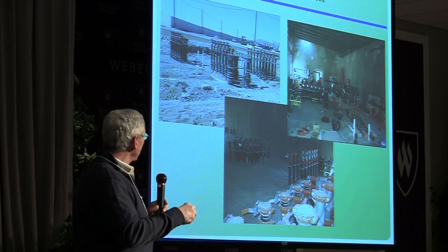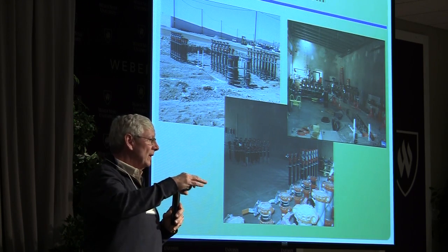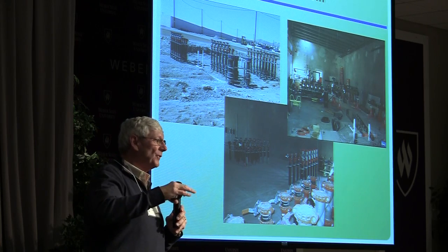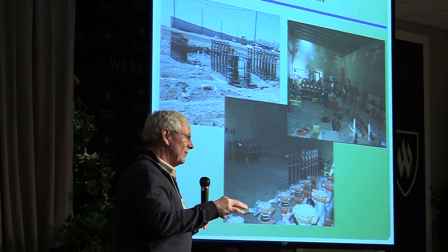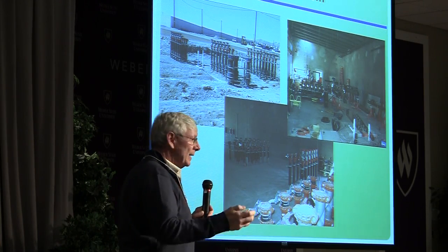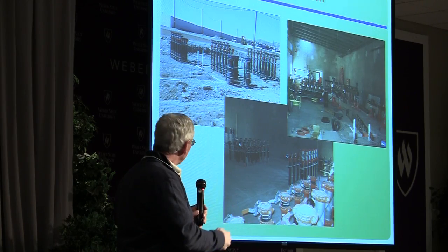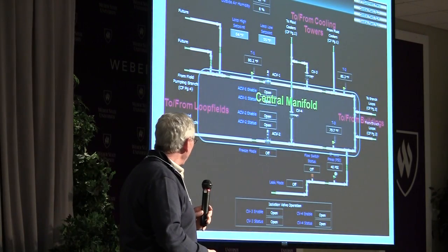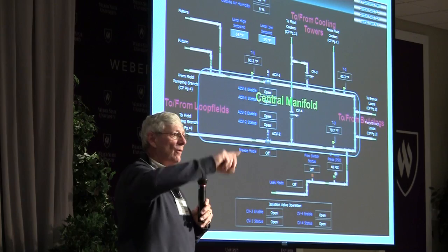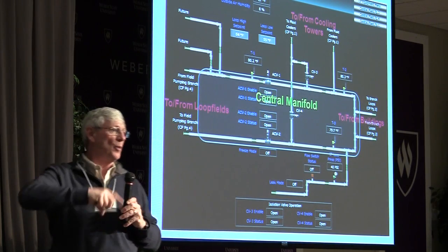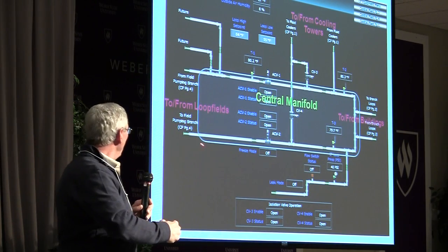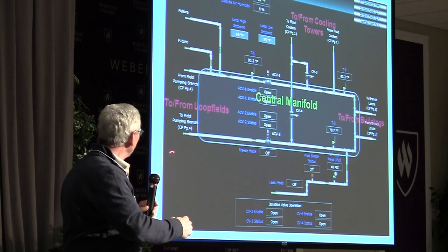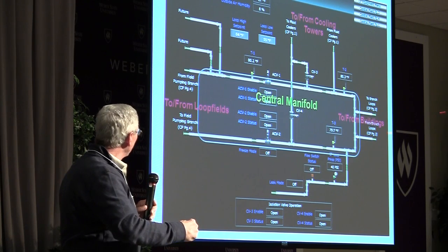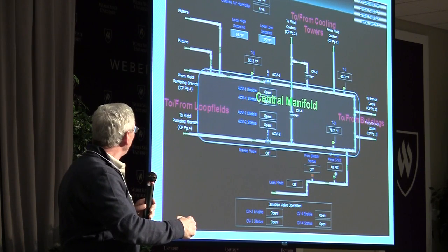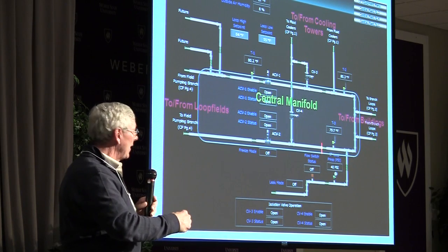This particular system has the ground loop covered with closed circuit fluid coolers, a type of cooling tower. So what we have is a central manifold that translates to our central loop, removing the fluid out of the bore field from here, and we're either taking it to the buildings or from the buildings. If we need it, we can kick in on our primary, secondary pipe.